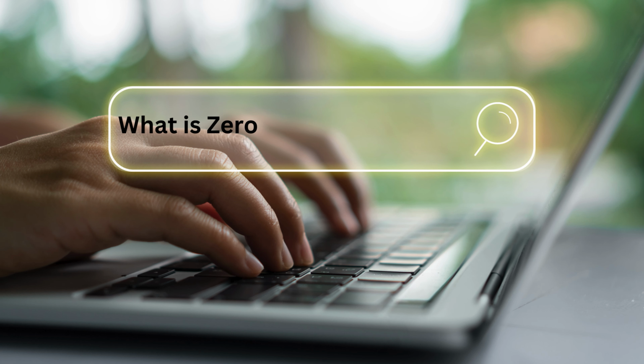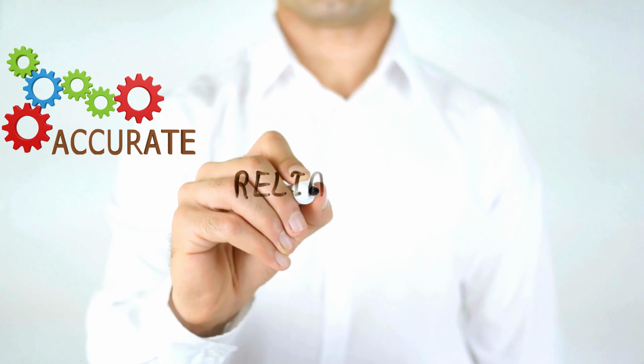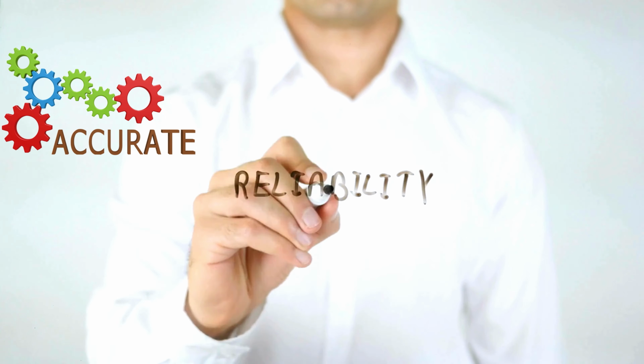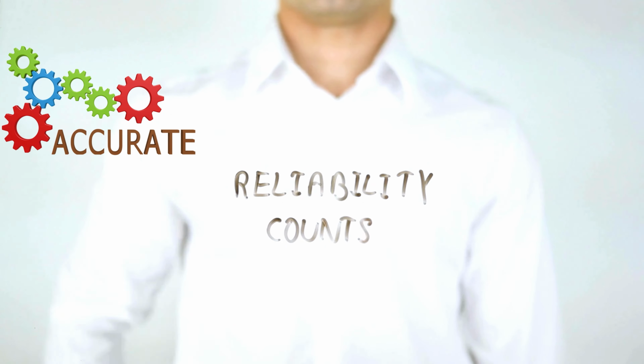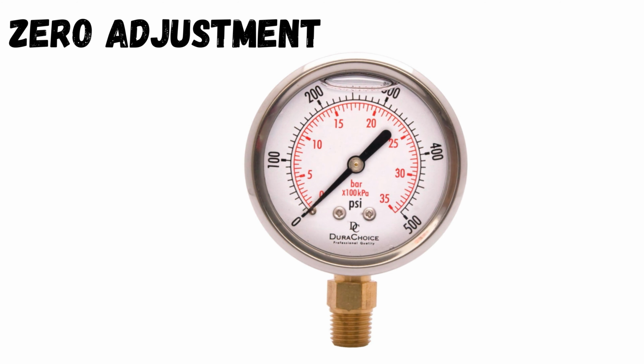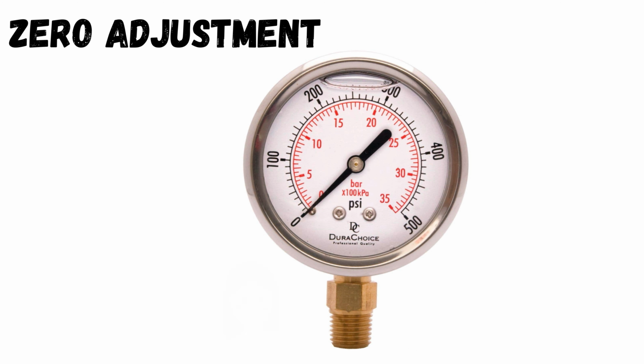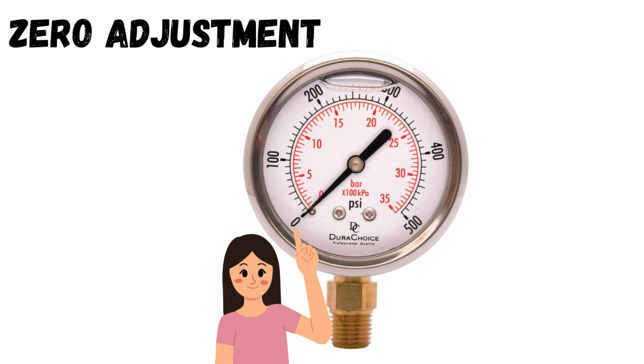What is zero and span adjustment? First, let's break down what zero and span adjustments are. These adjustments are critical for ensuring that your transmitter provides accurate and reliable measurements. Zero adjustment. This is the process of calibrating your transmitter so that it reads zero when it should. For instance, if you have a pressure transmitter, zero adjustment ensures that the transmitter reads zero pressure when there's no pressure applied.